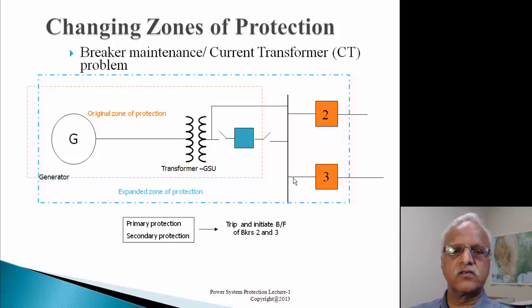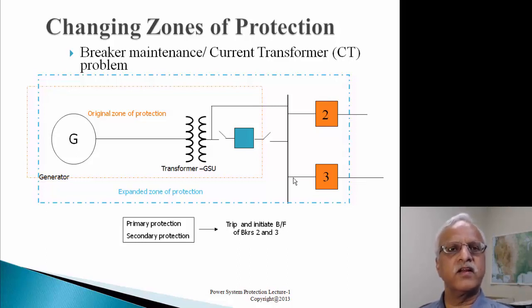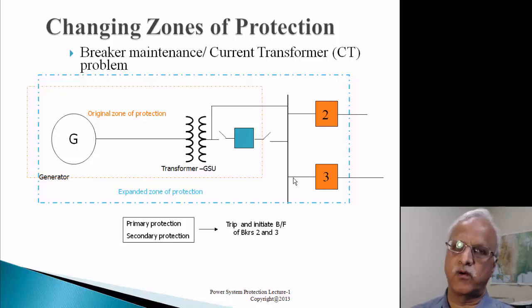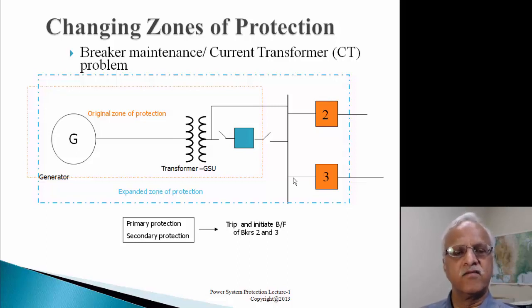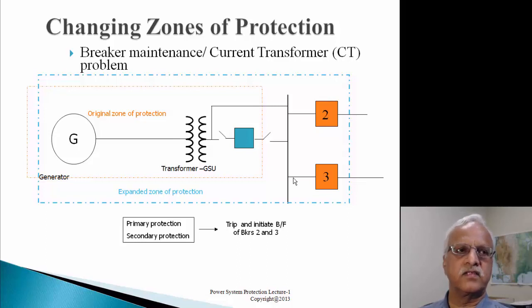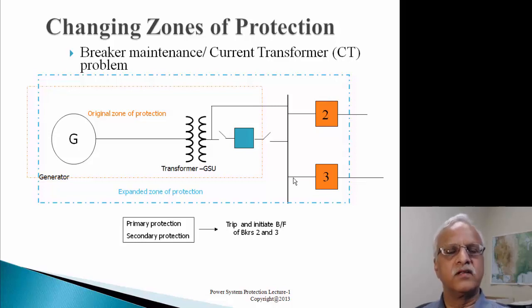We also need to initiate the breaker failure relay. The breaker failure relay monitors whether the breaker opened when commanded to trip. The primary protection relay sends an open command to the breaker and also notifies the breaker failure relay. The breaker failure relay starts a timer - breakers are supposed to operate in two to three or five cycles. If the breaker has not operated within that time plus a margin of a few more cycles, it is declared a failed breaker and the adjacent sources are opened.